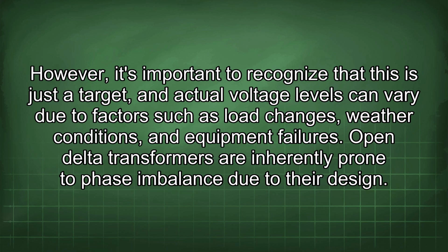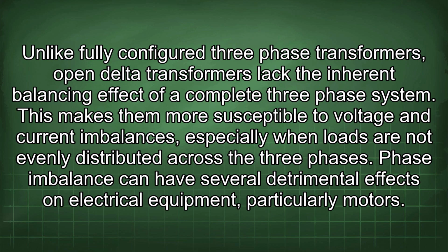Open delta transformers are inherently prone to phase imbalance due to their design. Unlike fully configured three-phase transformers, open delta transformers lack the inherent balancing effect of a complete three-phase system. This makes them more susceptible to voltage and current imbalances, especially when loads are not evenly distributed across the three phases.